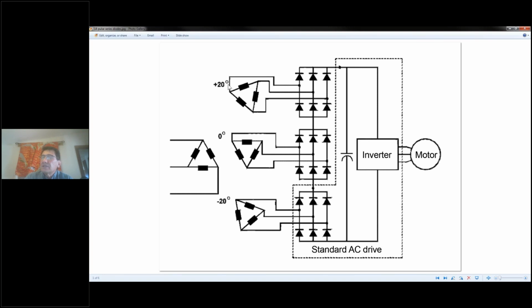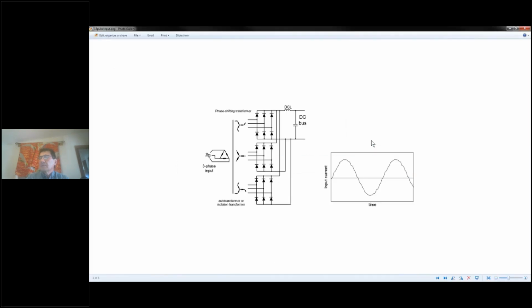In this particular case, the designer selected a 20-degree phase shift between the outputs. Again, you cannot connect these three AC outputs of the overall 18 pulse transformer. Well, you can, but you'll do it once. The fact is that the voltages are different because the sine waves are shifted. You can obviously connect the DC bus once we rectify all that AC to DC. In this case, series. In this case, paralleled.